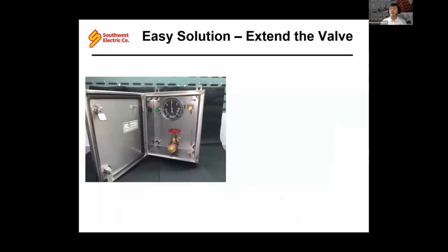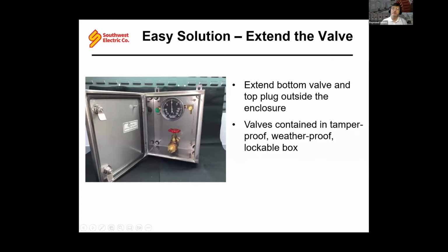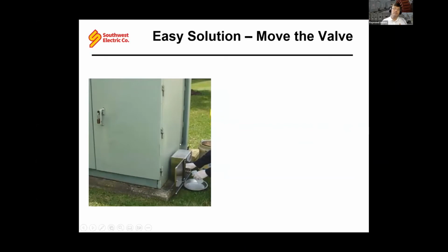So the easy solution is move that valve or extend that valve outside of harm's way. And that's where we would put in a separate valve in its own tamper-proof box that would be mounted on the outside of that cabinet. And by doing that, you can allow yourself to do the same kind of sampling you've always done, monitor your pressure, your vacuum on your transformer without accessing that cabinet, without even having to suit up. And so this is what that box would look like on a typical pad mount. And these are fairly easy to install.